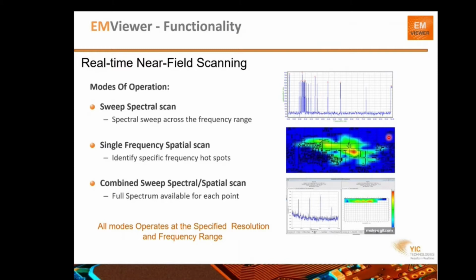I think we are very close to the live demo, but a bit of information about how to work with the tool, or with the software. So the first thing that you will do is actually a spectral scan. You would like to see which frequencies are present in your DUT or emitted from your DUT. You can define the range of the scan, and you can define the number of peaks that you want to identify. Usually a customer will choose 2 or 3 peaks, the highest ones.